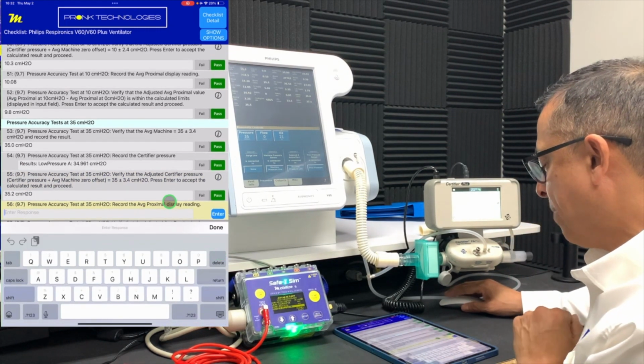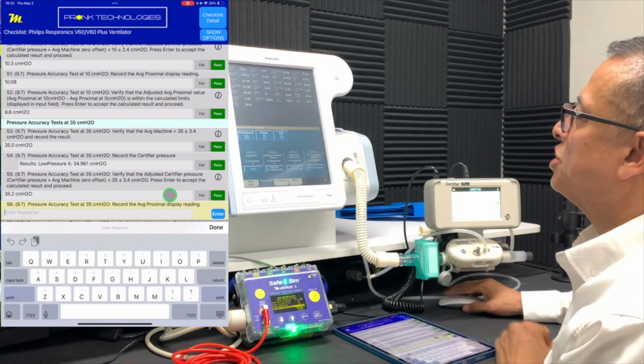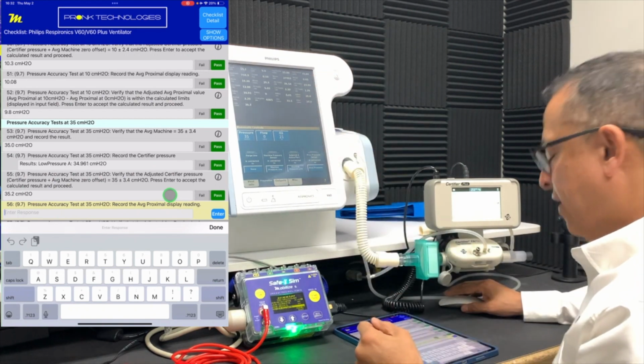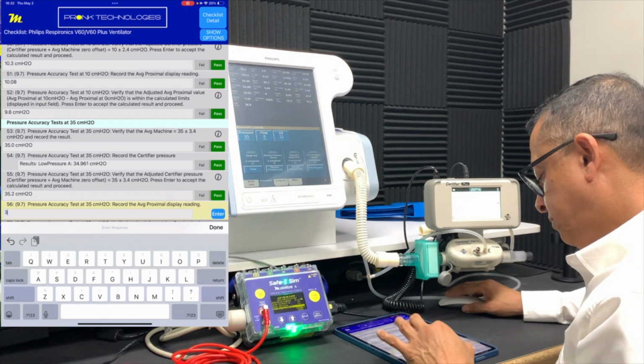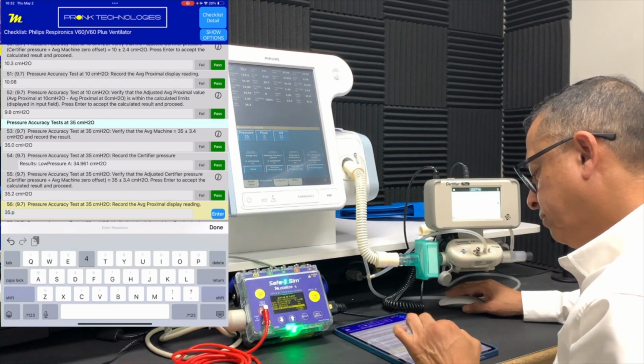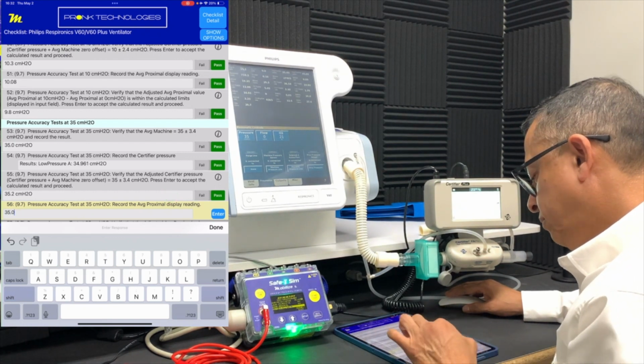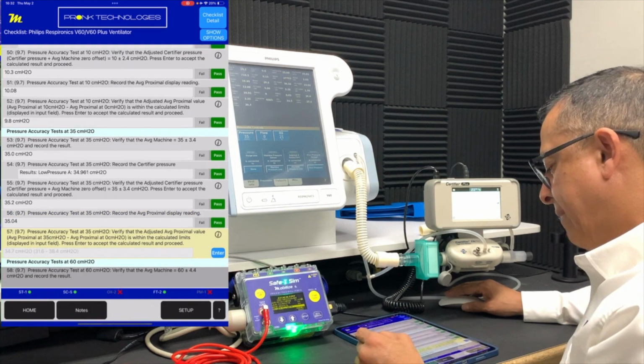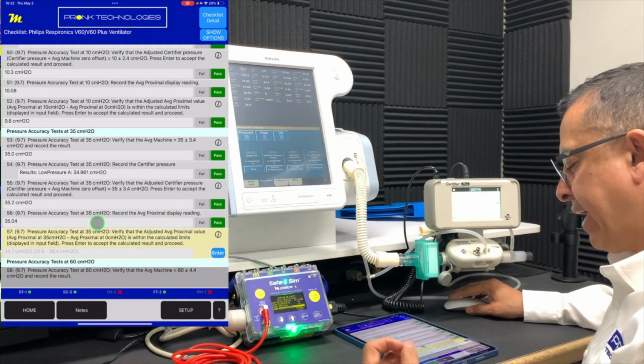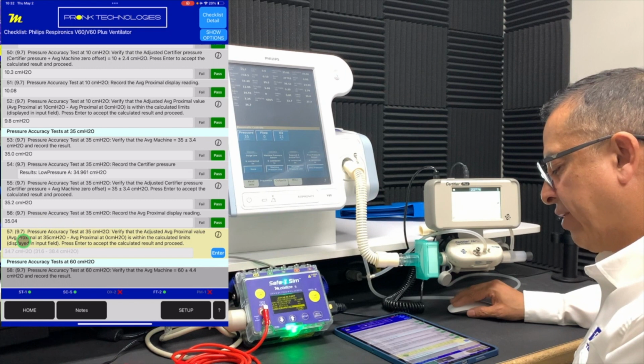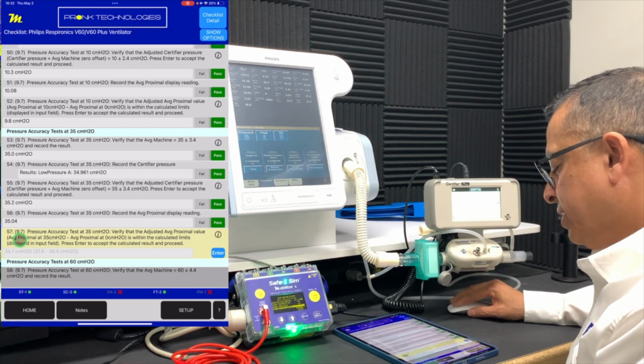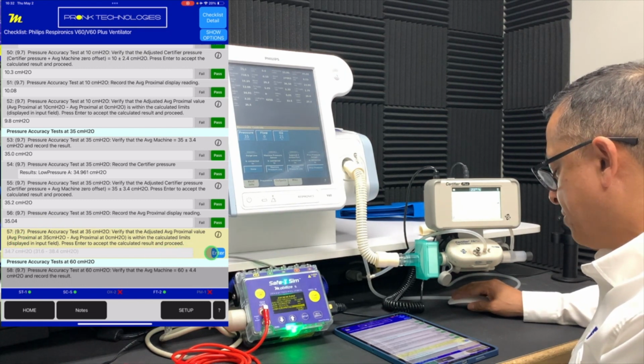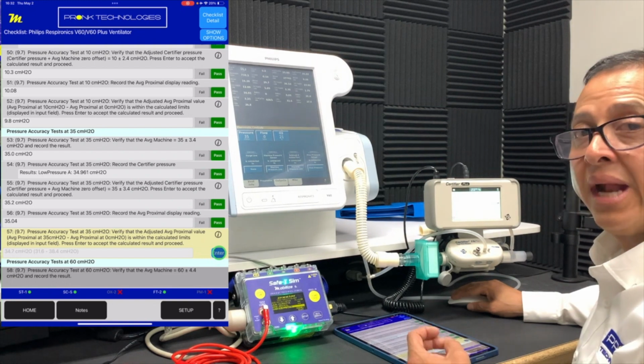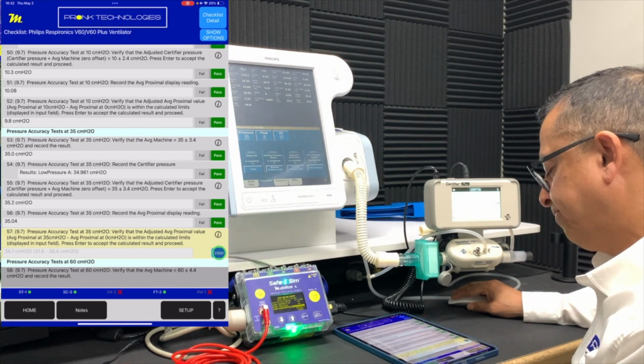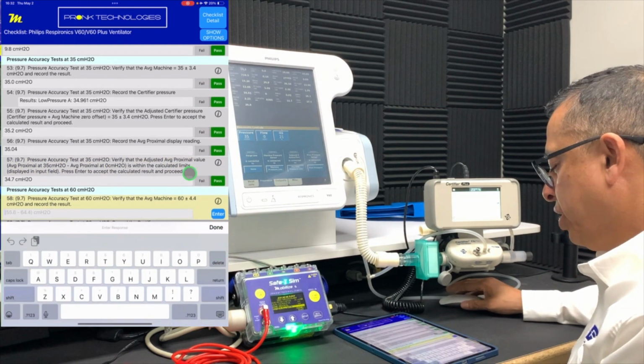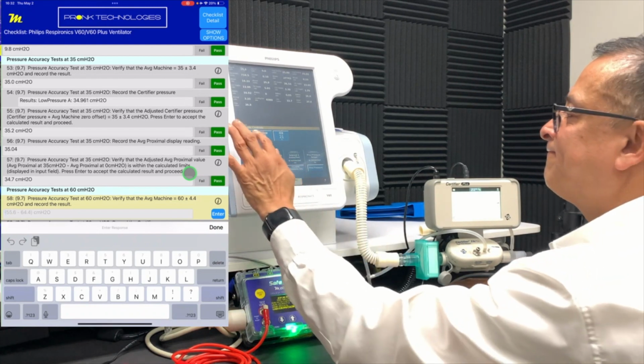And we now need to measure the proximal pressure as well. That is at 35.04. Capture that, and you can see there's another calculation. We've gone ahead and done that calculation here as well. So there's various calculations that have to be captured, and we've captured them all automatically via the checklist we're running here. Now we're going to do the next test at 60.